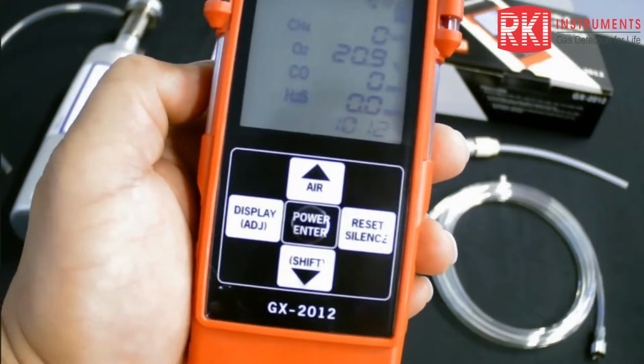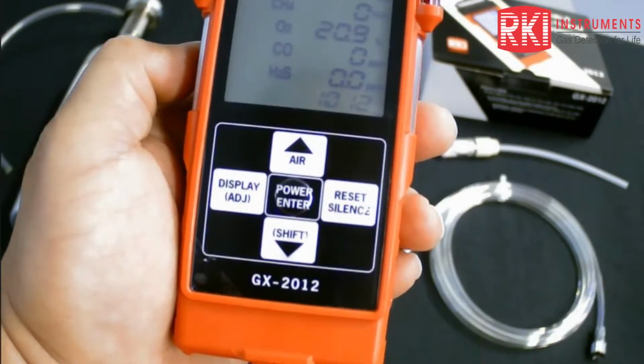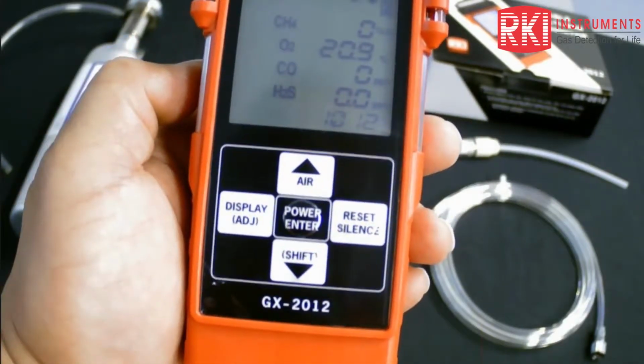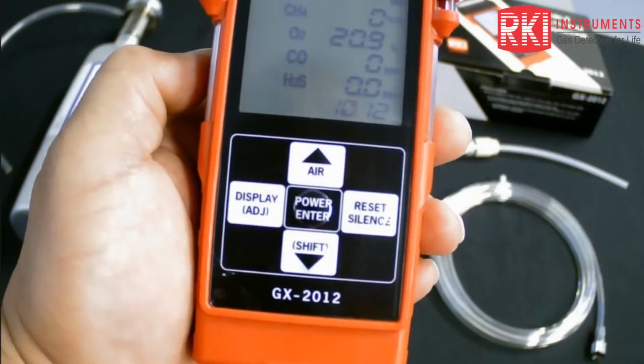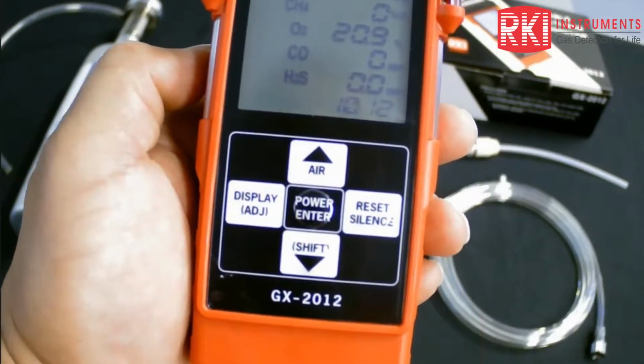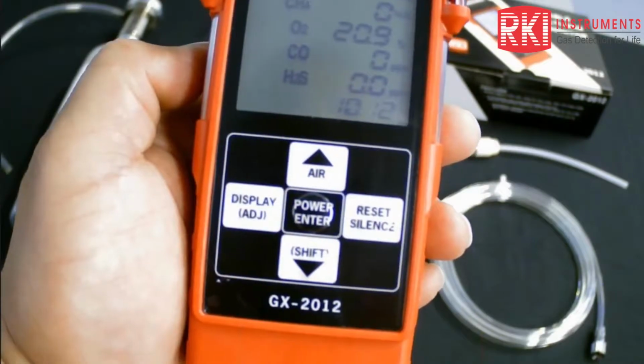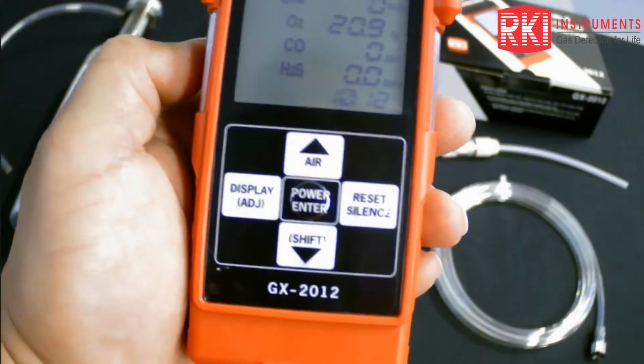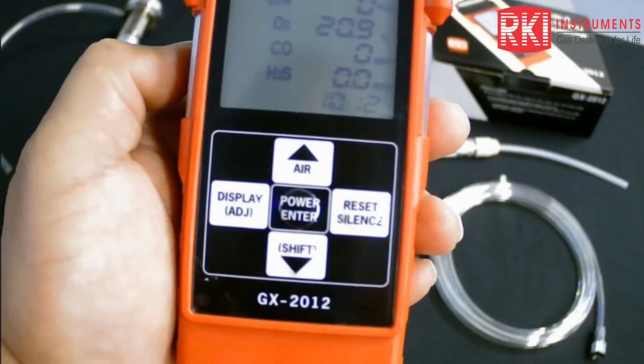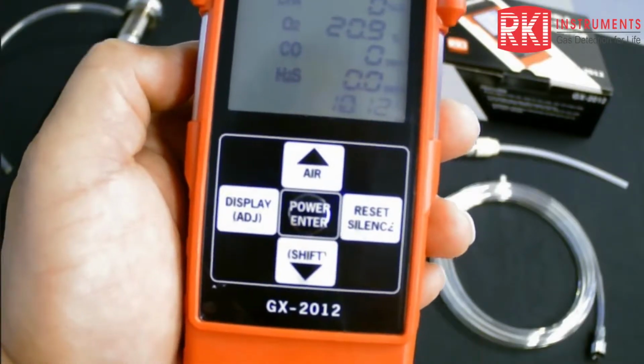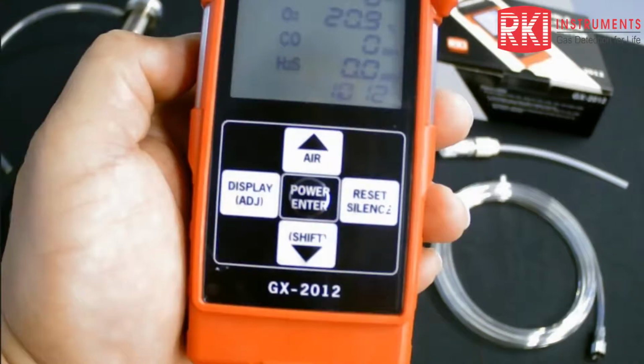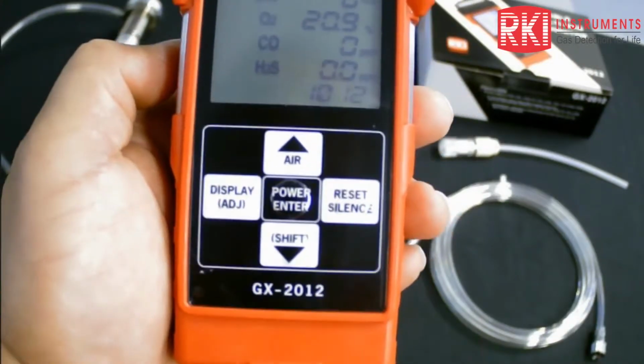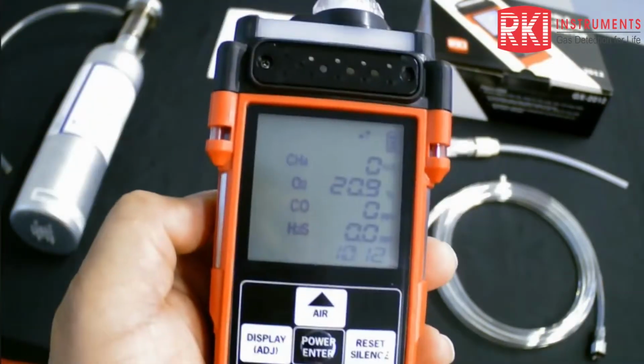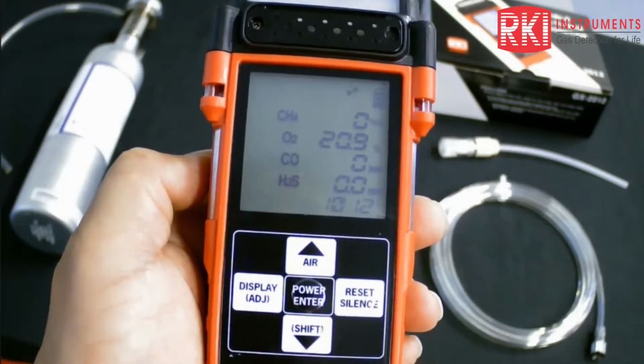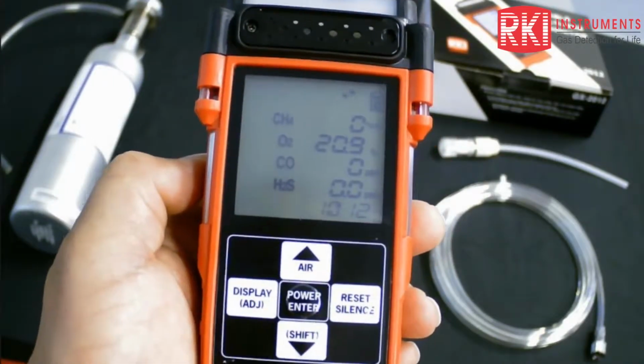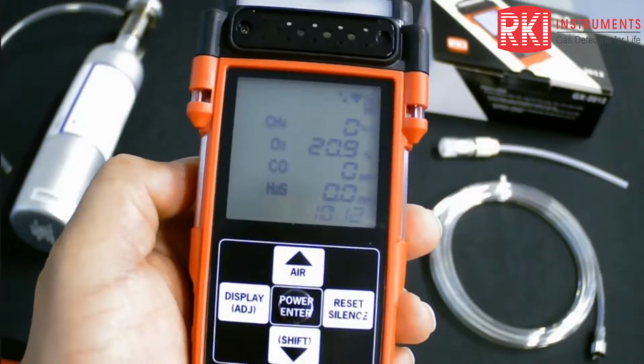So basically that 100% LEL range is equal to 5% by volume for methane. So if you have a thermal conductivity sensor for the high range, basically that is an auto-ranging function in this unit, as John Maslowski mentioned. And basically you would see the display go from 0 up to 100% LEL. Once 100% LEL is exceeded, the units will switch from LEL to percent vol, is what you would see on the display, and continue on up, theoretically up to pure gas, 100% volume, if you had that much gas present. Okay, so you do have a huge capacity for measuring the concentration of the gas.